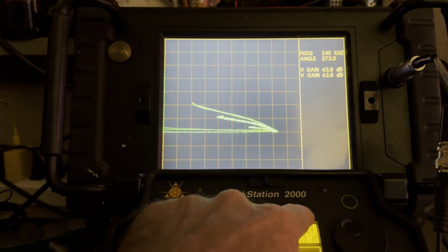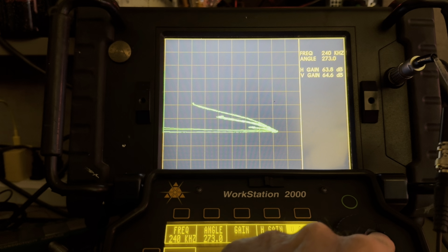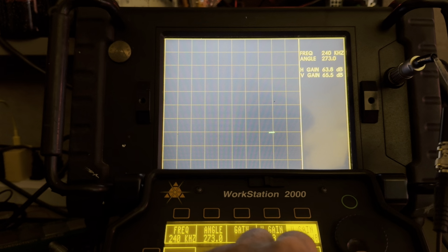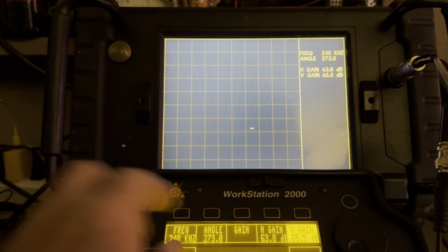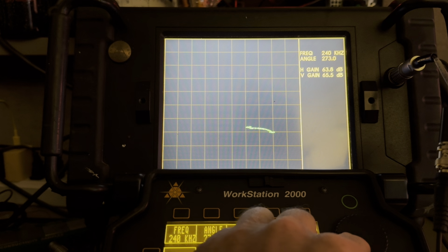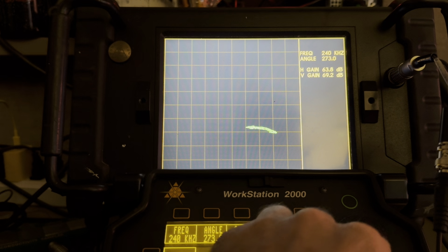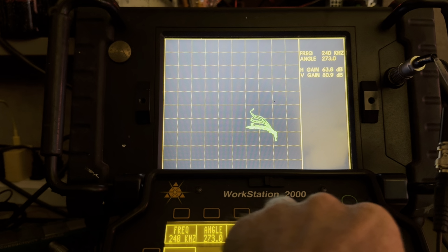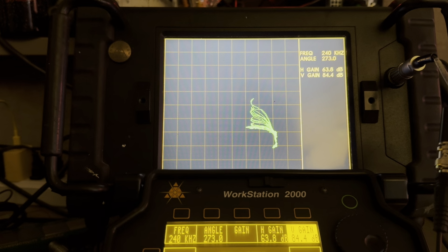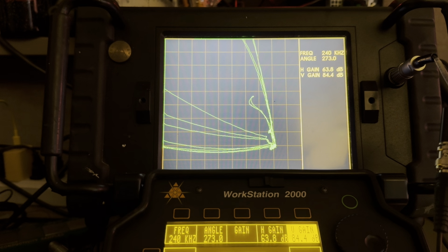So how you can remedy that is crank up your vertical gain by itself without the horizontal gain. And what you'll see as I scan over, I'm going to scan over the shallowest notch. Right now it's what, 4 degrees? As I start to crank up my vertical gain, you're going to start to see that separation angle between liftoff and that 8 mil deep EDM notch increase. And our liftoff is still relatively flat. So now you can see you got about 80 degrees separation, and that's the shallowest flaw. There's your 20 mil and there's your 40 mil. So basically we're set up pretty well to do a bolt hole scan now.